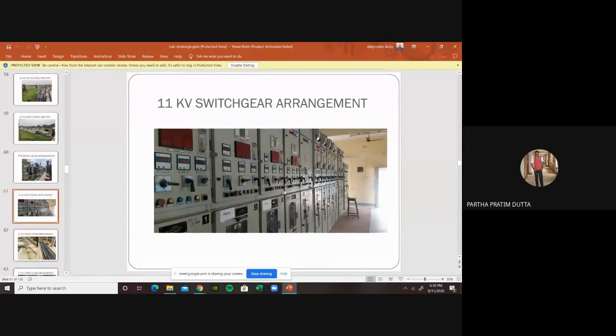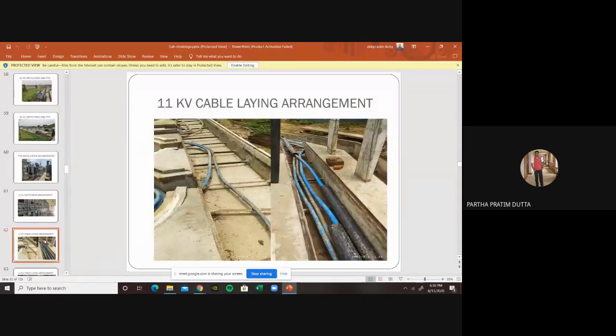And this is the 11 kV switchgear arrangement. As I told you earlier, this is the 11 kV cable laying arrangement. All the 11 kV cable which comes out from the 11 kV switchgear is laid into the cable laying arrangement of the switchyard. This is called the tunnel of the cable, and it is placed on a rack made of iron channel. We prepare the rack, and the cable is laid through the rack, and then run to the end of the substation.